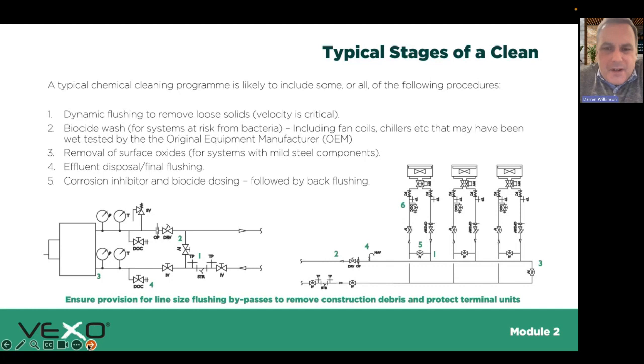But a biocide is rather like an antibiotic. If you consider that the system could have slime in those terminal units, and bacteria, flush the system first at velocity, add your biocide, and what typically happens is the contractor will then backwash, forward wash into the coils, get the air out of the coil and leave it then with biocide. Then they close those coils off, go back to bypass mode. And then whilst the rest of the clean's happening, you've essentially given those units a shot of antibiotic.